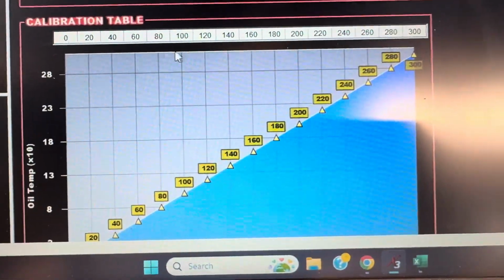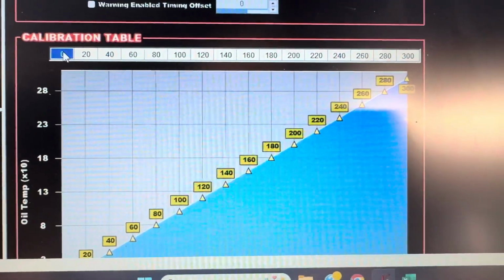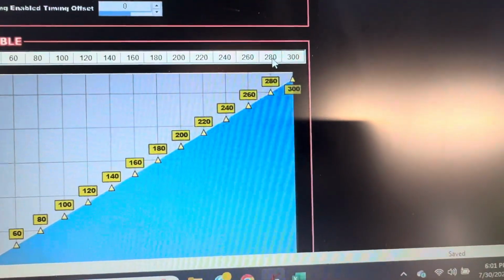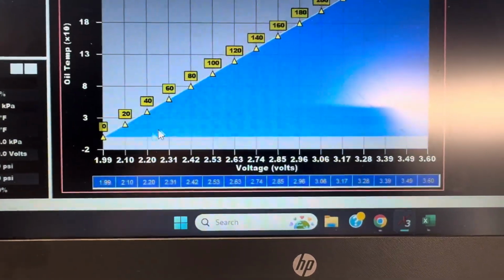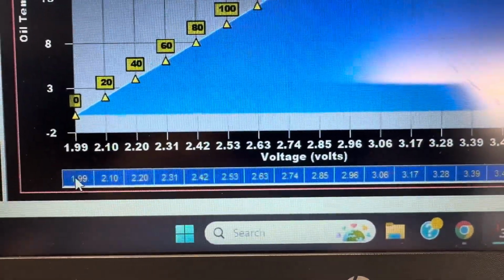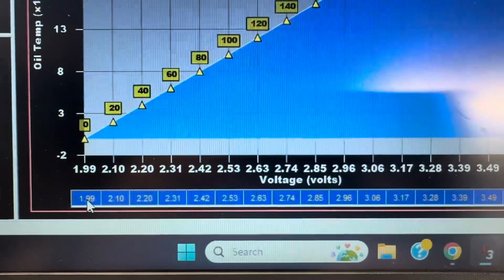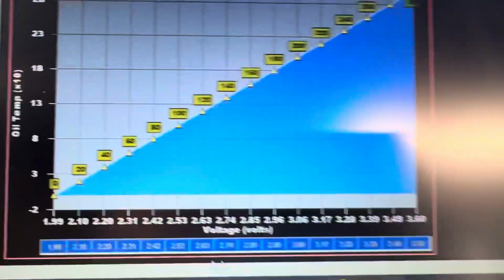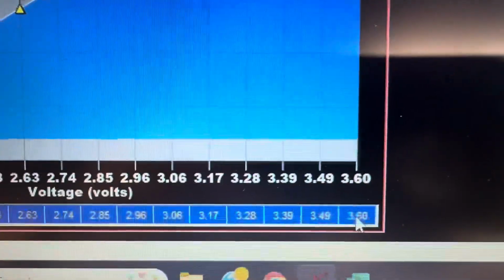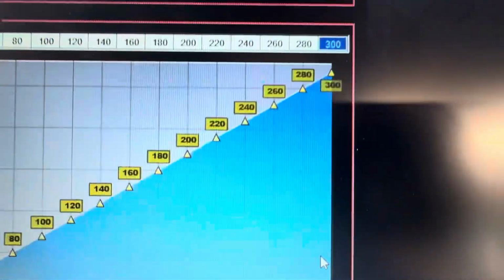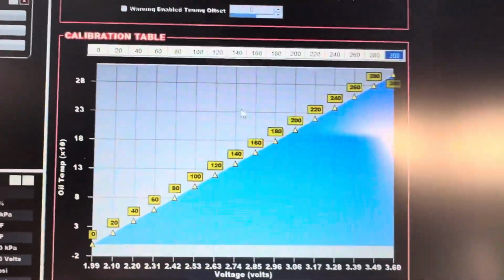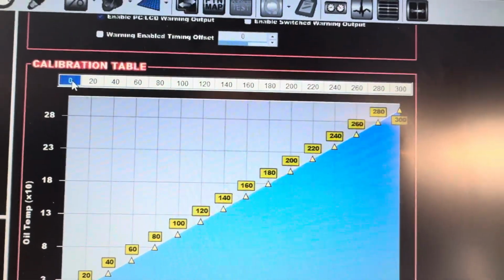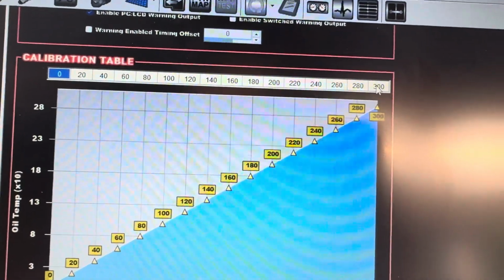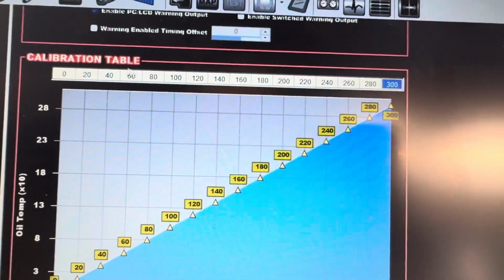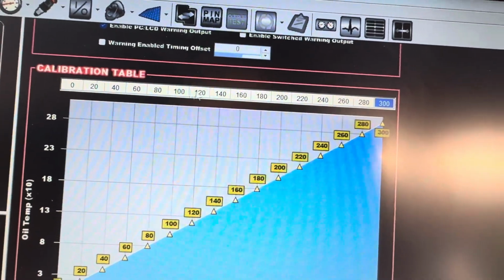You're basically putting the same numbers in here: 0 degrees Fahrenheit to 300 degrees Fahrenheit as the max, and 1.99 as the min voltage corresponding to 0 degrees Fahrenheit, up to 3.6 for 300 degrees Fahrenheit. The key is to put that min and max temperature on either end, then go across.